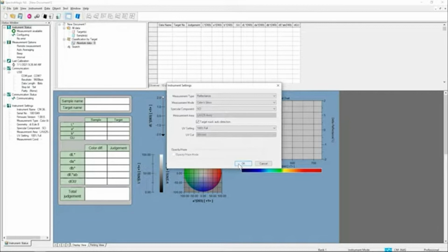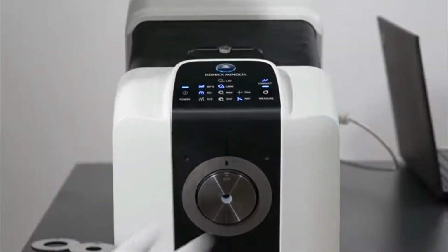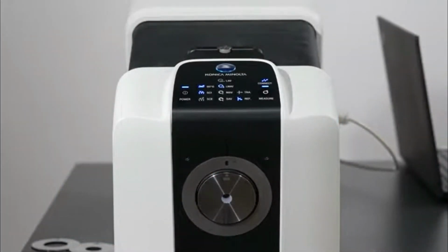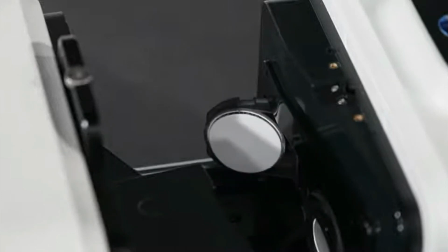You can also use the software to turn on the target mask recognition option. When this is active, you can change the mask on the instrument, and it will automatically update the mask indicator on the instrument's display.